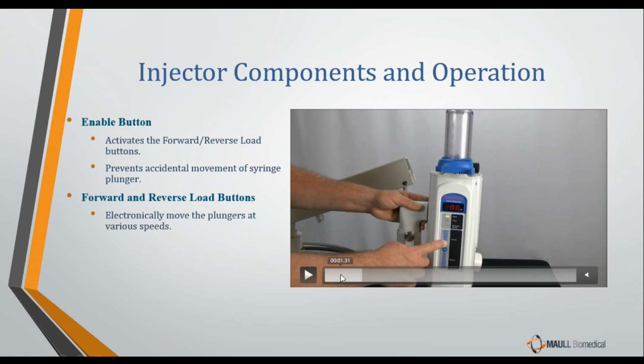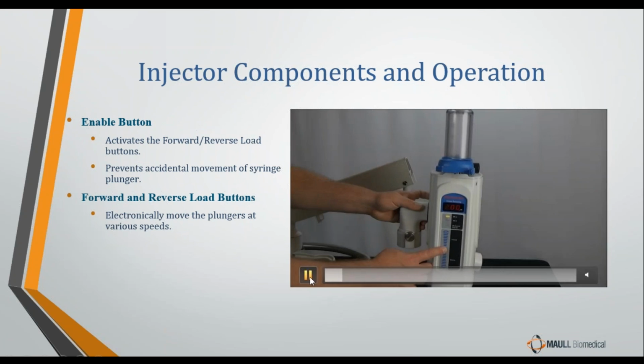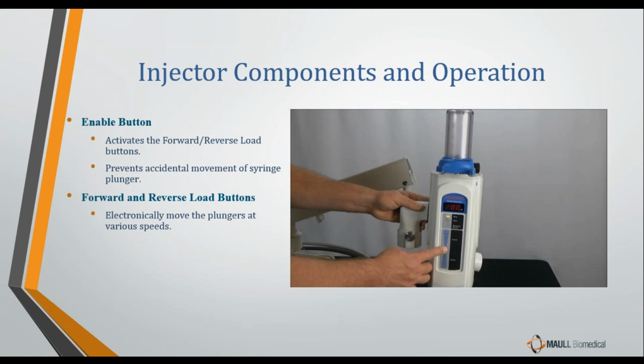First, the enable button and the forward and reverse load buttons. The first thing the operator has to do is hit the enable button. Its purpose is to activate the forward and reverse load buttons, which don't function until the enable button is hit. That's a safety feature, because we don't want the injector attached to the patient and then someone grab the injector head to move or rotate it and accidentally push the load buttons, pushing or pulling fluid into or out of the patient. So they are deactivated until the enable button is pressed, and once it is pressed, they become active.